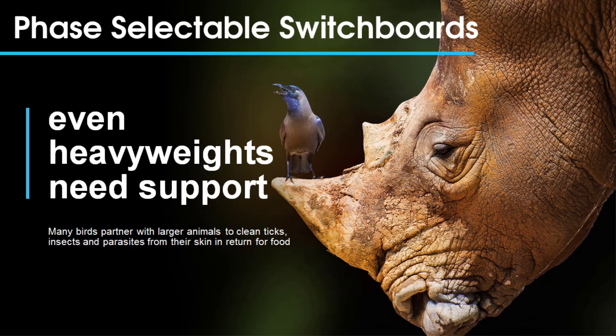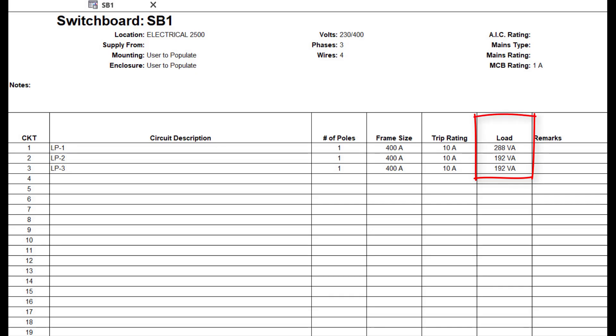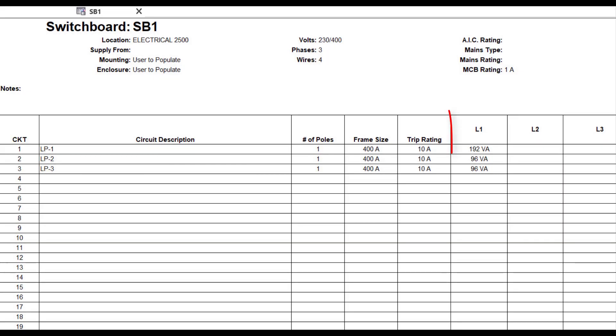Next let's take a look at phase selectable switchboard circuits. With electrical distribution in Revit MEP, a single phase distribution board fed from a switchboard will always connect to the first phase. The default panel schedule for switchboards in Revit MEP is set to only show the phase that's being used, therefore left as it is we only ever see phase one. Even if the schedule is modified to show all phases, there was not a way to move panels to a different phase.